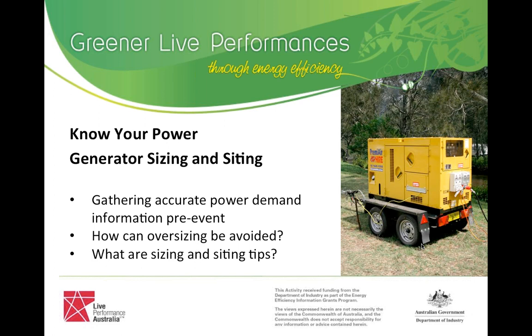That's something I've been discussing with a lot of event organisers: if there's mains power available, that's what you want to take first up and put your 24-hour loads onto, because then you can actually shut your generators down. That's definitely a key trick. With the concept of energy efficiency, how would you describe it at the types of events you're involved with? Are you talking about optimising generator loads, or using energy-efficient equipment to reduce total generator sizes?